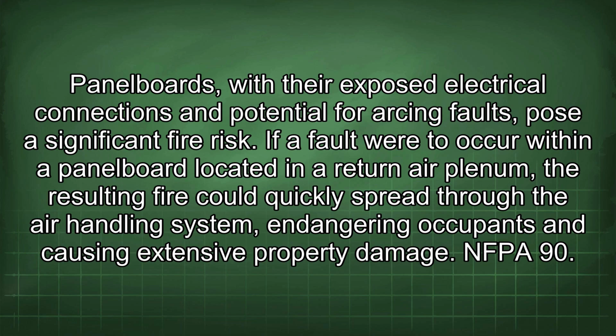Panelboards, with their exposed electrical connections and potential for arcing faults, pose a significant fire risk. If a fault were to occur within a panelboard located in a return air plenum, the resulting fire could quickly spread through the air handling system, endangering occupants and causing extensive property damage.